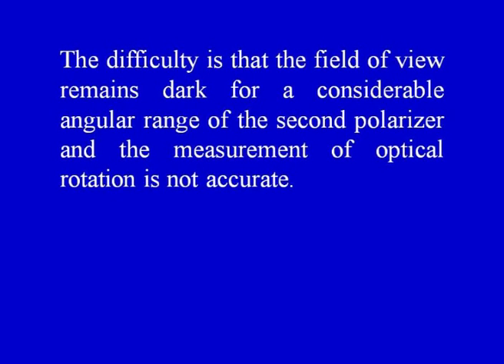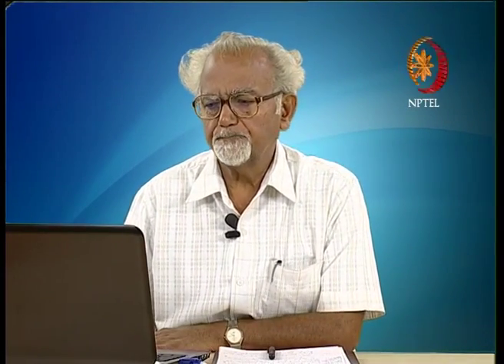The angle of rotation can be measured by fitting a circular scale to the second polarizer. However, in practice the field of view remains dark for a considerable angular range — sometimes plus or minus 10 degrees — making measurement inaccurate. There is no provision for comparison of intensity between two regions side by side. Polarimeters are designed with this feature to measure the angle accurately.